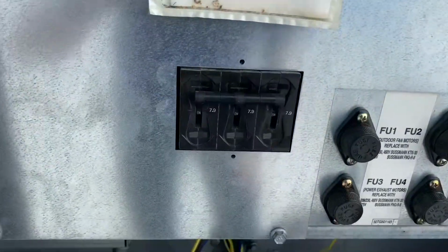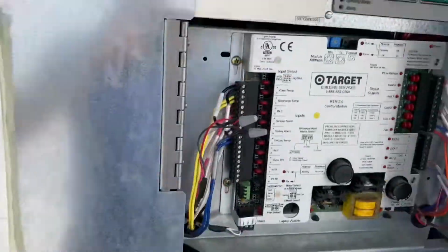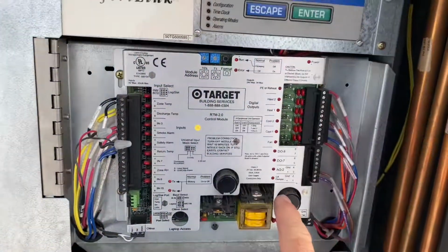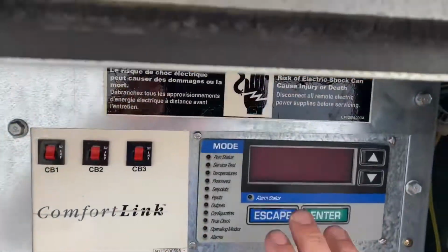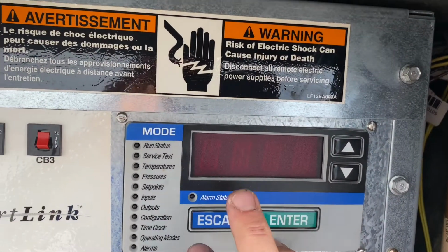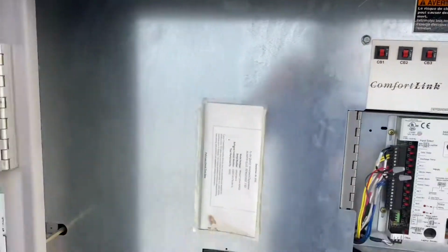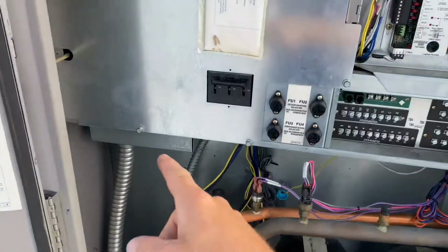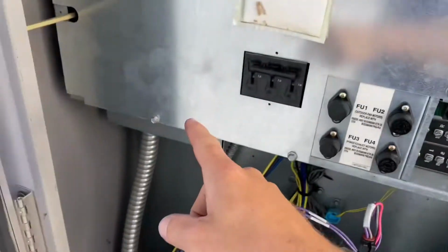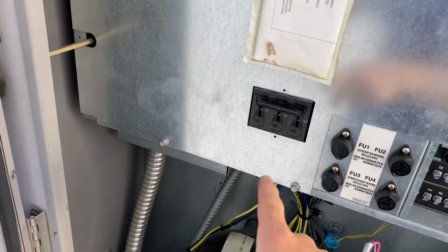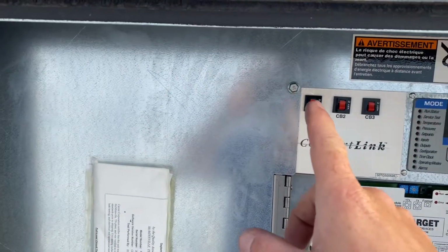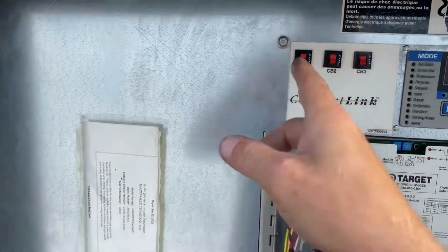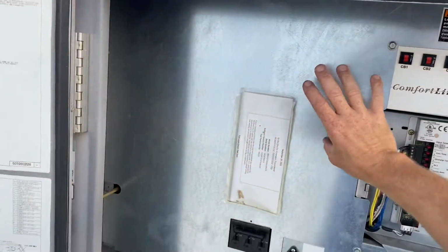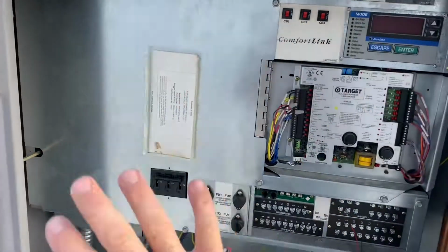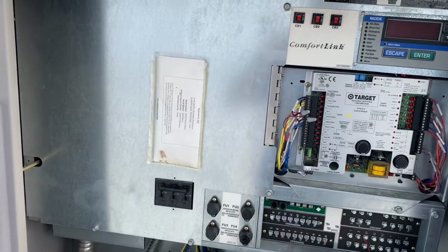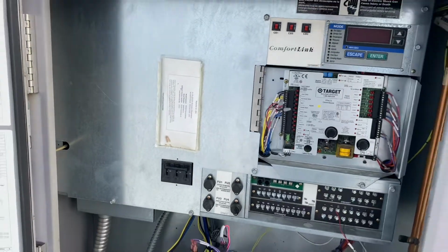This breaker is also on, not tripped. No power on this communication board. So what we'll do is pull this cover off. Just got a few bolts. Sometimes they're not all in, depends how many people have had their hands in these things. But take these bolts off, get this main cover off, exposes all the electrical components back there, and get some readings on it. We'll start from there.